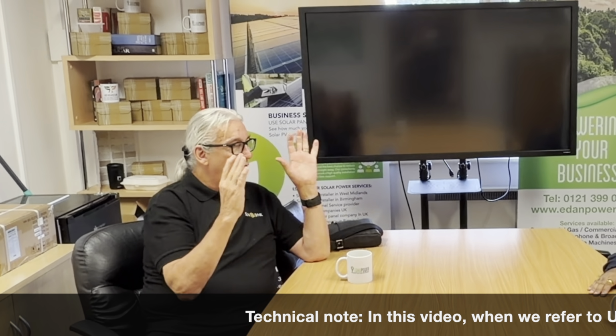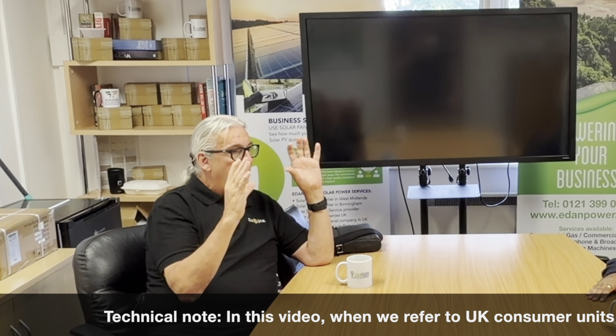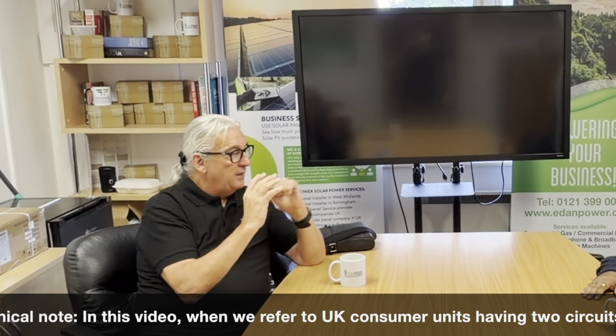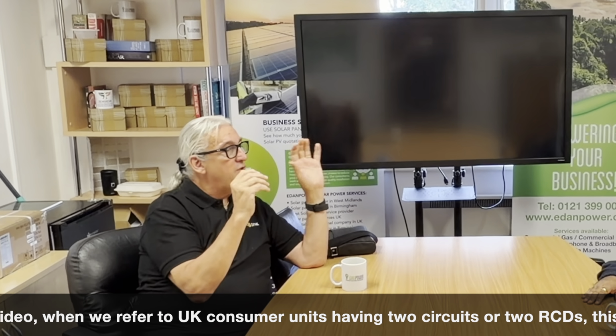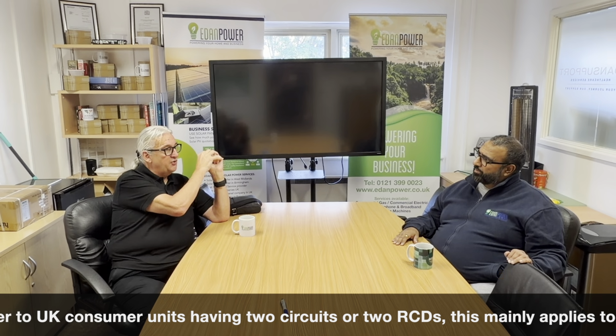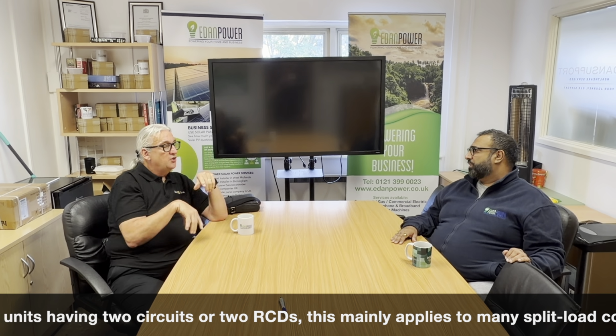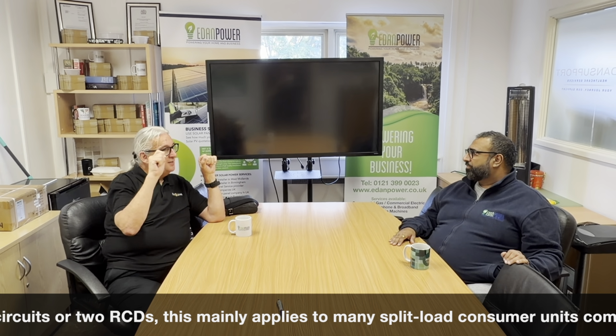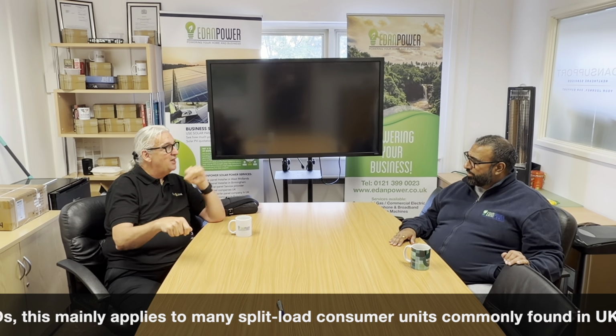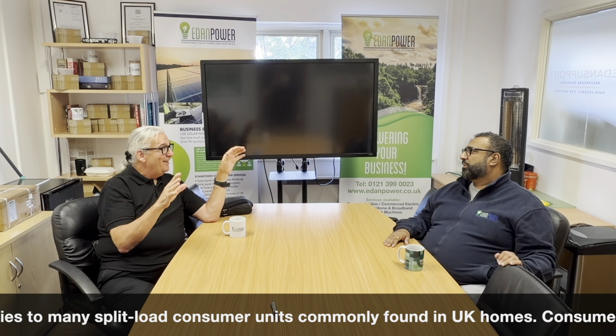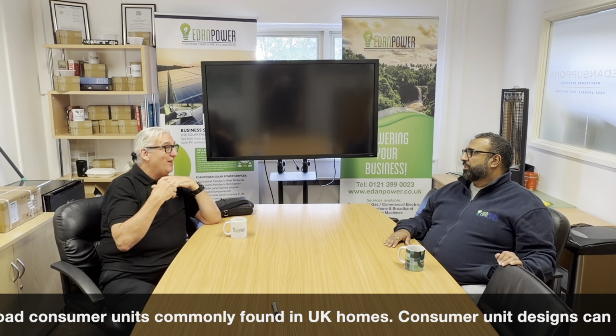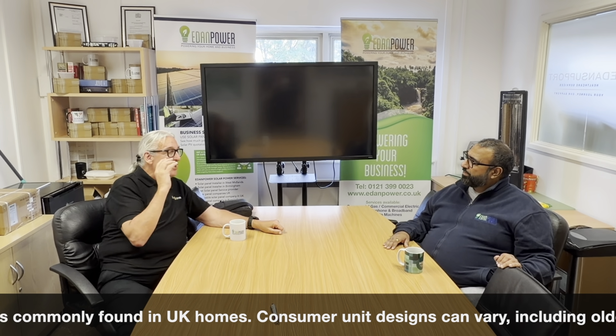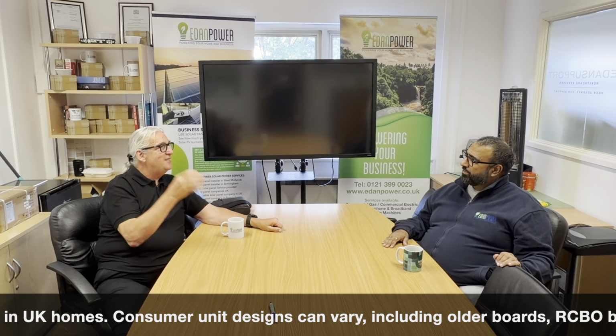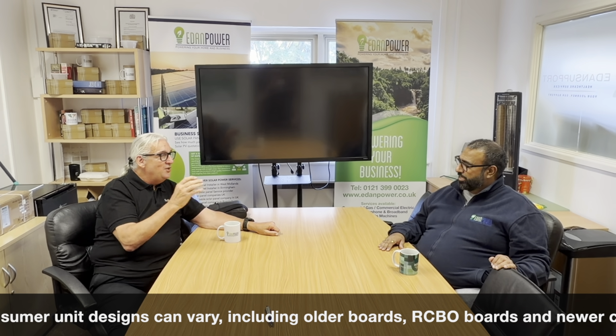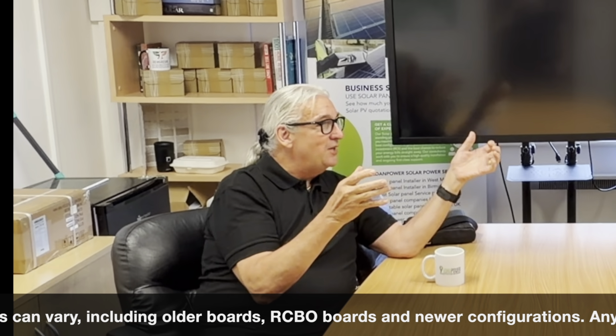Most UK fuse boards have a split, two RCDs, two circuits in it. So all you do is take one circuit into the load connection of the inverter, the other side goes on that, that's it, dead easy as a sparky. That's amazing, the UK is the easiest one to wire into, you don't need a gateway, all the consumer units are already done.